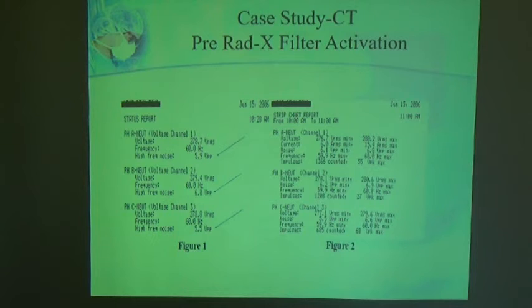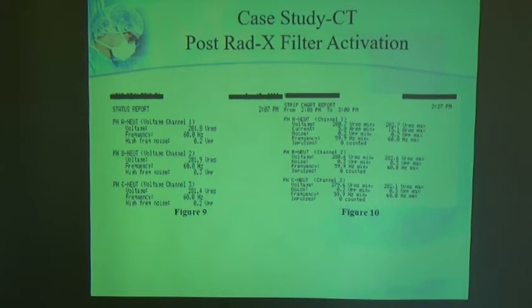Looking at this pre-Rad-X filter activation, what we see is high-frequency noise as high as 6 volts peak to peak during idle. During operation of this piece of equipment, we see that high-frequency noise rise even higher to a level of 6.9 volts peak to peak max. We also see several thousand low-level voltage impulses being produced. The Rad-X filter being activated, now in idle mode we see 0.2, 0.3, 0.2 volts peak to peak high frequency noise. And when the equipment is operated, we see that that noise remains low in spite of the equipment being in operation. Also, there are no voltage impulses recorded during that operation.